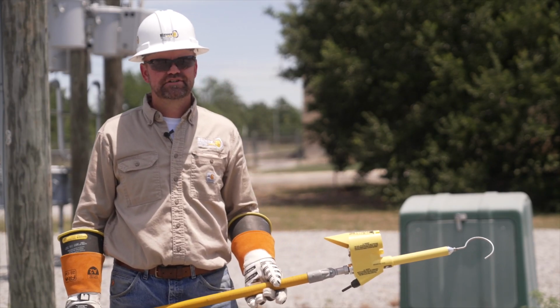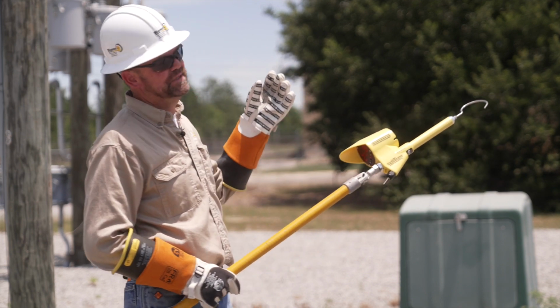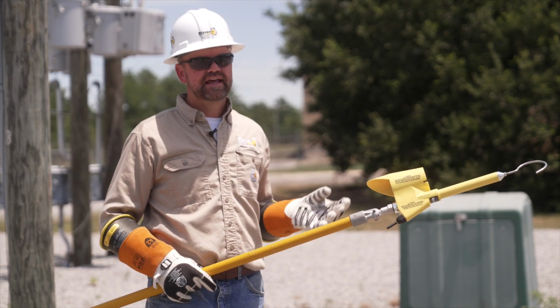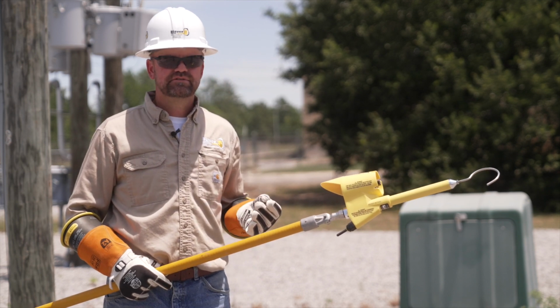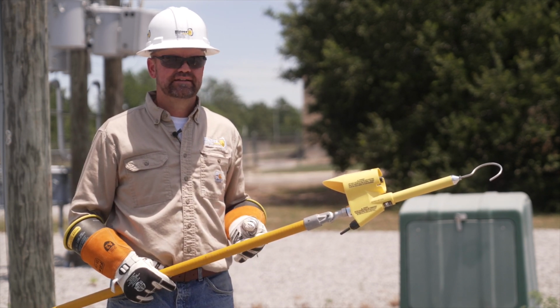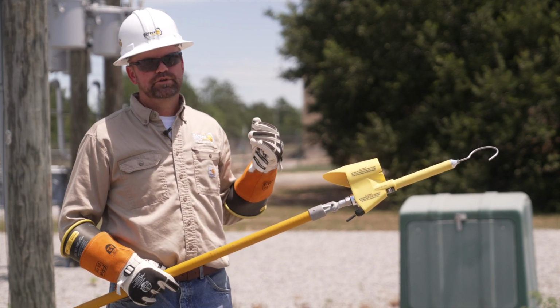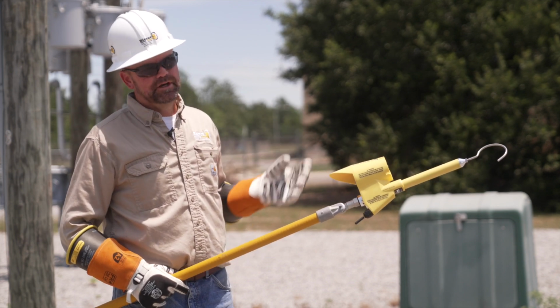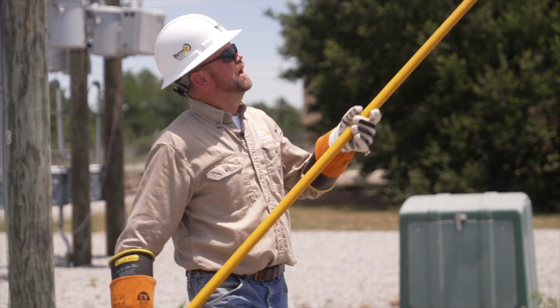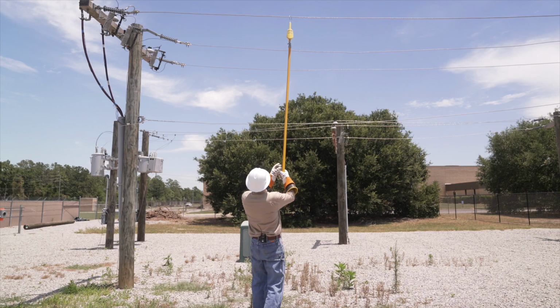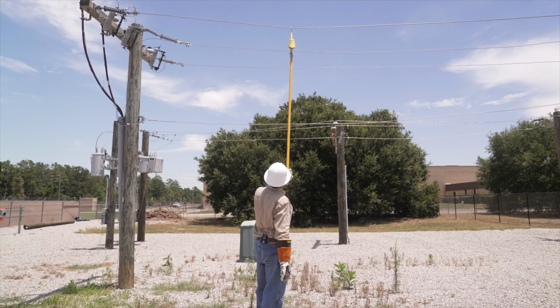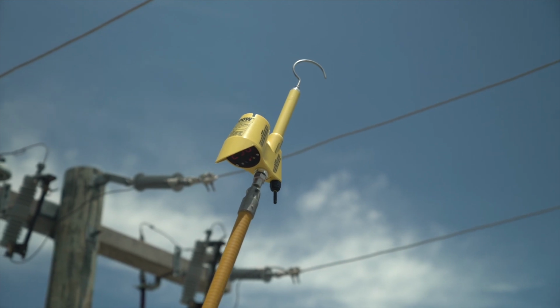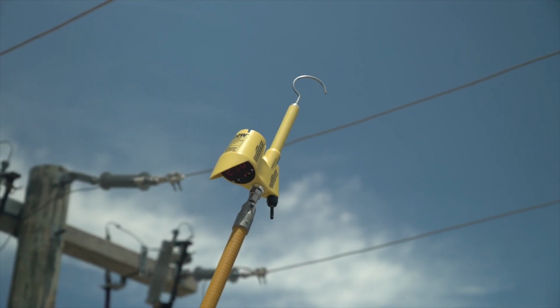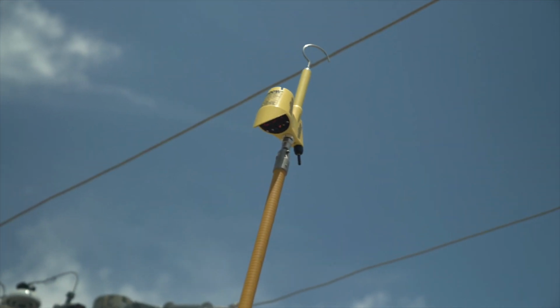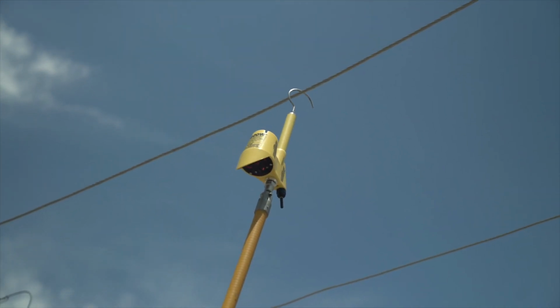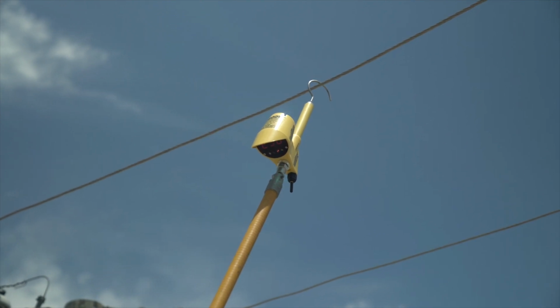Okay, so just a moment ago I showed an issue we had where this outside phase was being induced from the middle phase, and the phase angle was not what we would call a pretty phase angle. We had a flashing yellow light. So I fixed the problem. We found where the problem was at. We fixed the problem. And now I'm going to come back and see if my phasing is correct. So I'll try this outside phase again. You'll notice I already have a red light, which is my 240 light. In other words, I start detecting the phase at basically near minimum approach distance before I physically contact the phase. If I land the probe on the conductor, I have my solid red light, my near 240 degrees.